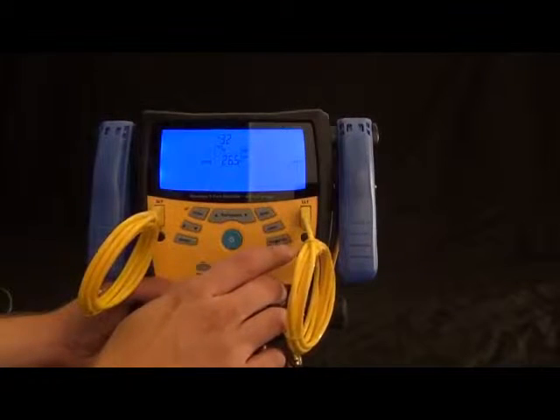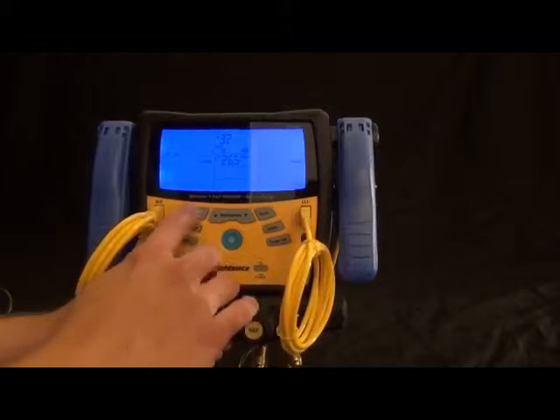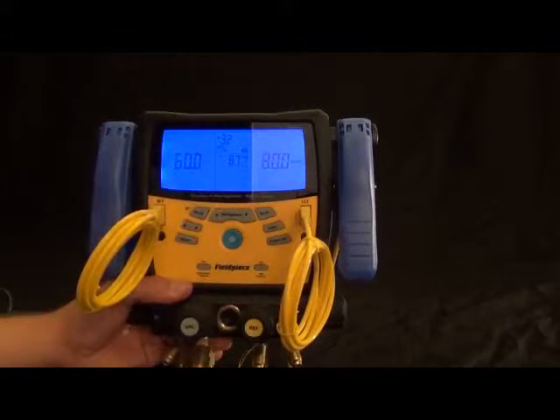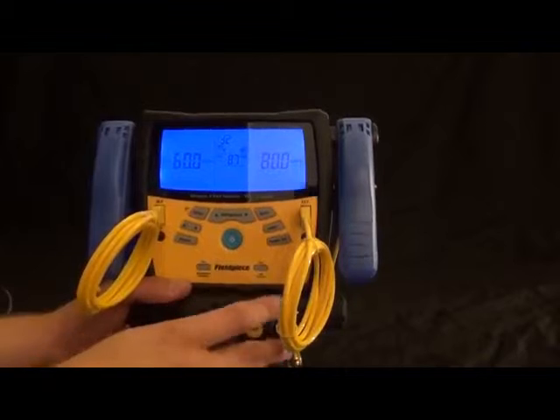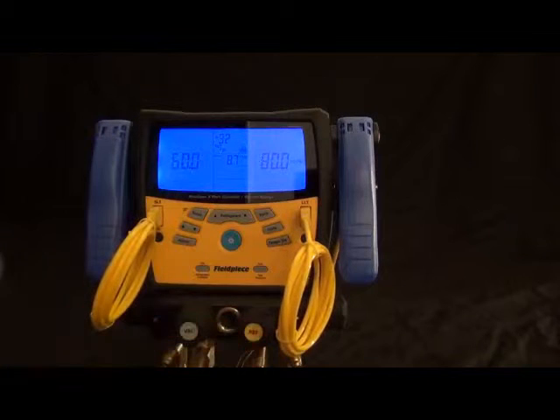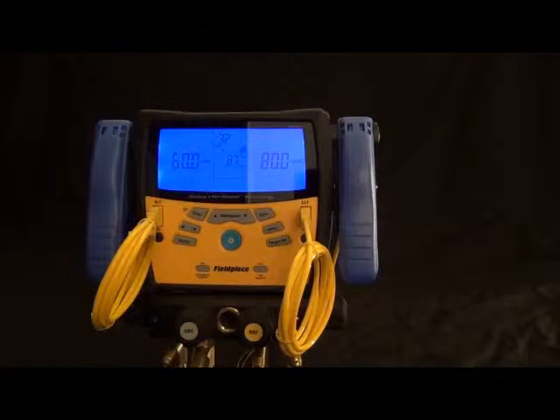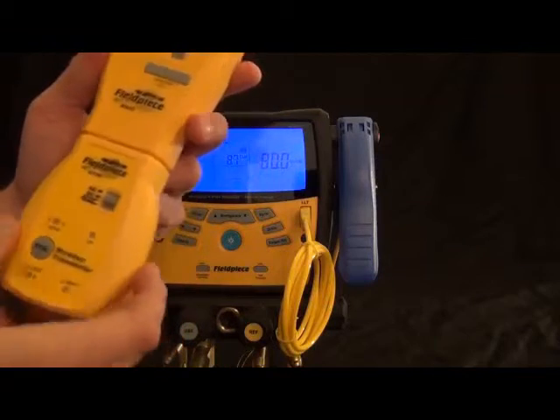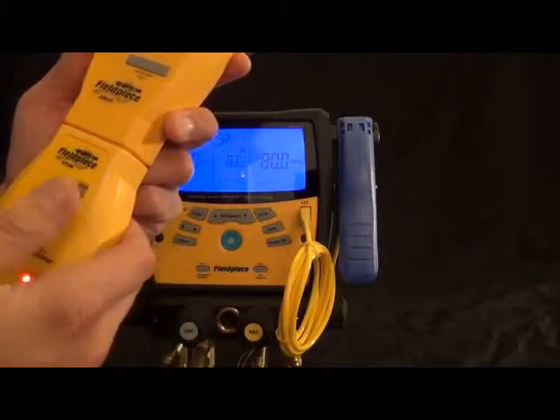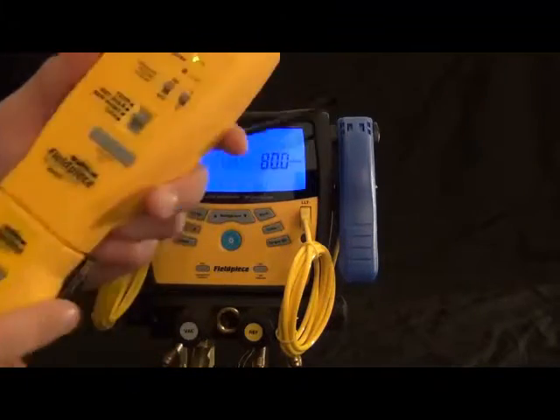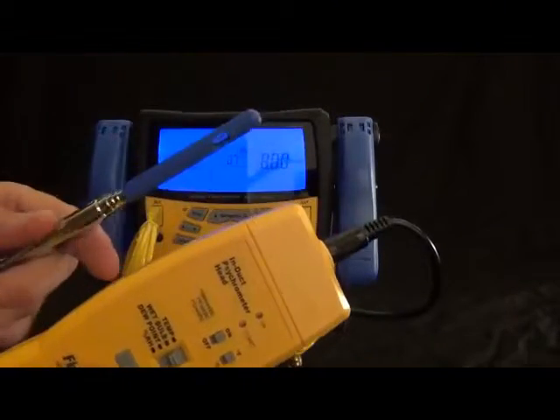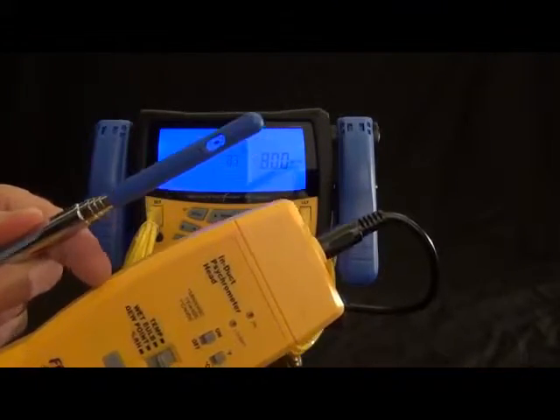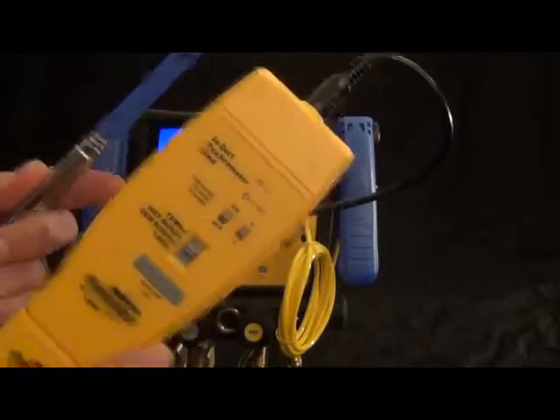What I can do is put this up in the attic with the air conditioner out in the garage or wherever it is, and send a wet bulb measurement outside. So, let's just go ahead and do that. First, I'm going to press sync on here. You'll see it searching. I'm going to press sync on my transmitter, and you'll see that pop up in just a couple seconds. There we go, I got a 60.9 degrees of wet bulb.